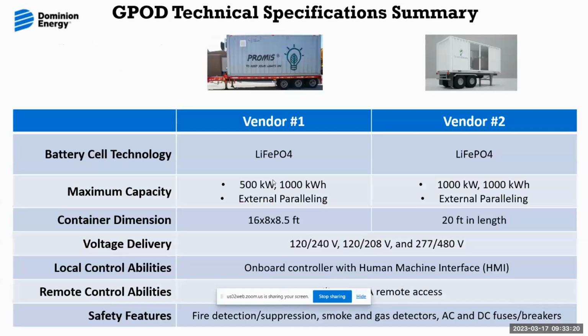To see in reality what these look like, these are 2 vendors we're looking at for the project. Both are lithium iron phosphate batteries, a little different in sizes. One, vendor 1, has a peak output of 500 kW but a duration of 1 megawatt hour, or 1,000 kilowatt hours. The other can do a peak output of 1,000 kilowatt hours, basically taking a 1,000 kilowatt punch but only serving it for an hour.